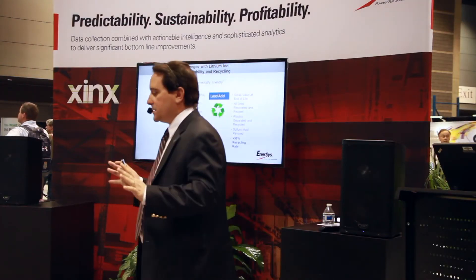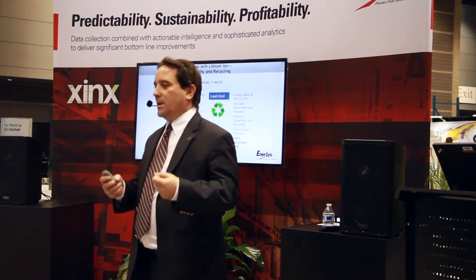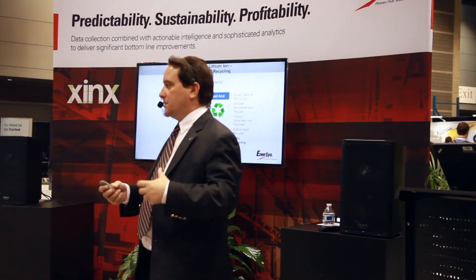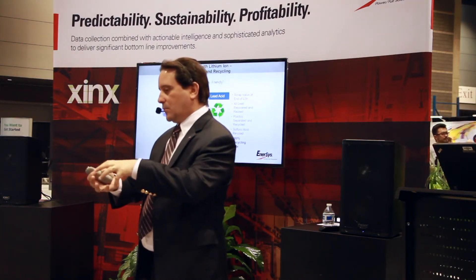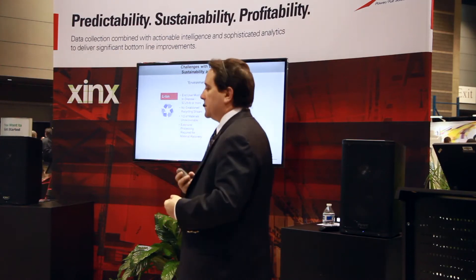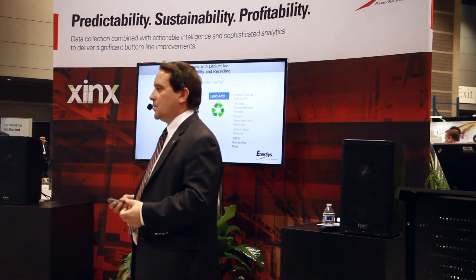Here are some comparisons of lithium-ion and lead acid batteries in terms of sustainability and recyclability. Lithium-ion batteries today — if you show up at a smelter or reclamation center, you're going to be paying money to have them take those batteries off your hands. They have to disassemble them and dispose of several items. If it's a cobalt technology, they might try to reclaim some cobalt as a rare earth element. But there is really no established recycling stream like there is with lead acid, and it's a pretty extensive process to try to recover them today. There is a lot of work going on in the industry to try to address this, but it's just not there yet.